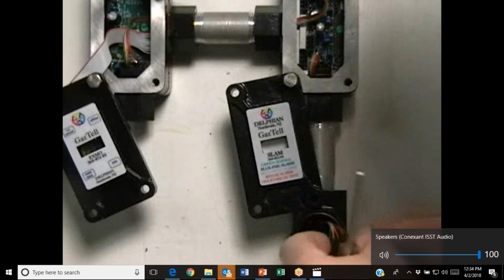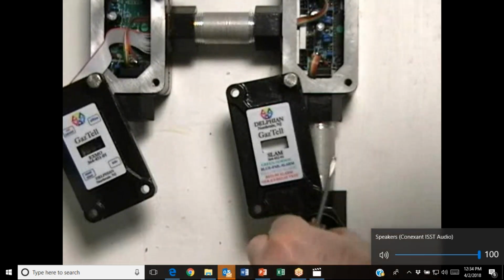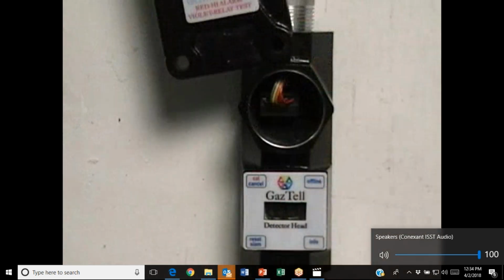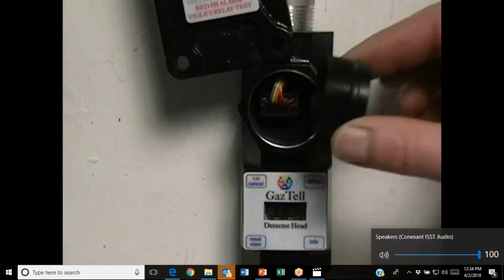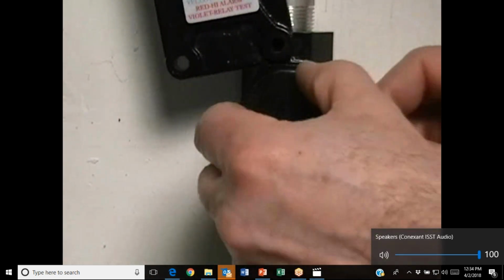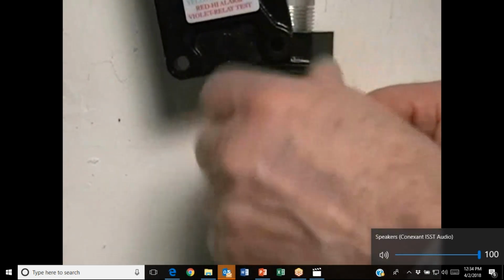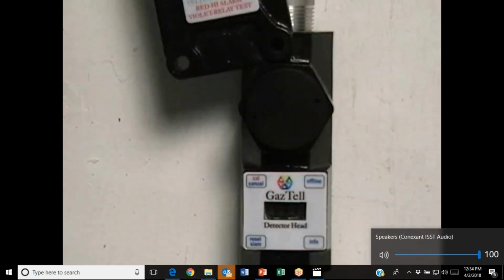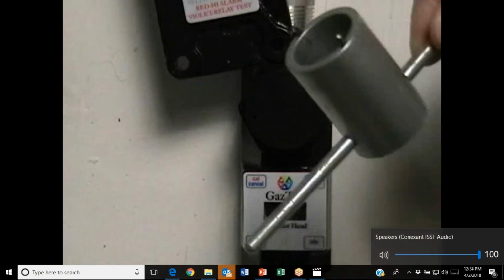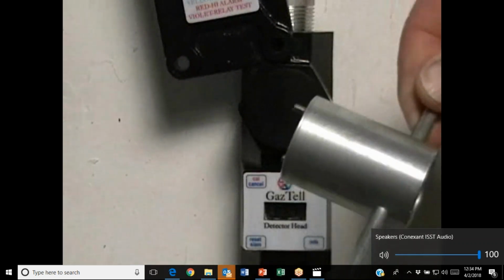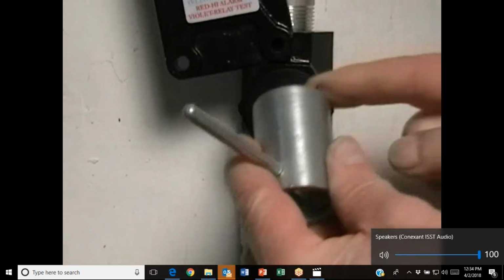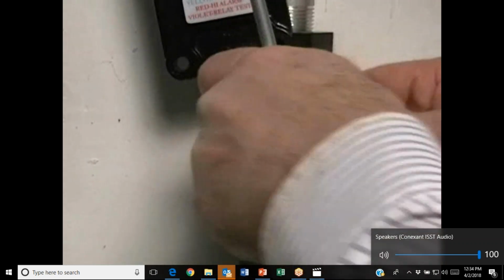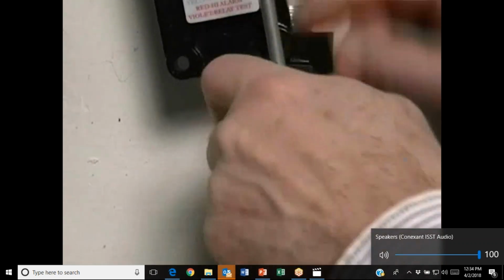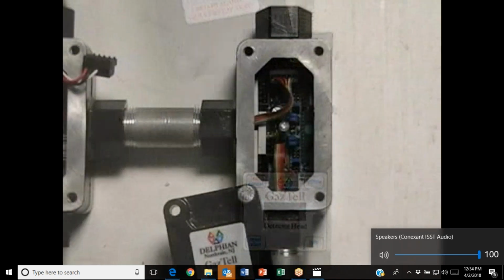Once all the cables are connected, you can make the last connection to power and power up the system to make sure all the modules turn on properly. For this video, we will close them all up before we supply the power. The detector access port plug is reinstalled into the body first by hand, and then secured using the optional flame arrestor access port tool. This tool has 2 pins that easily insert into the plug or flame arrestor to easily tighten them.